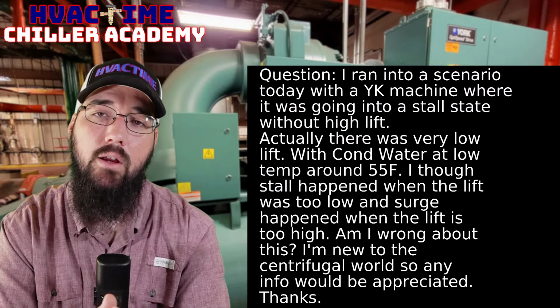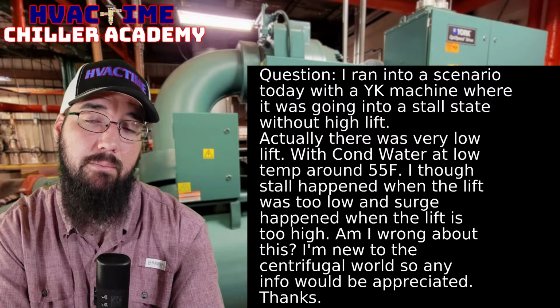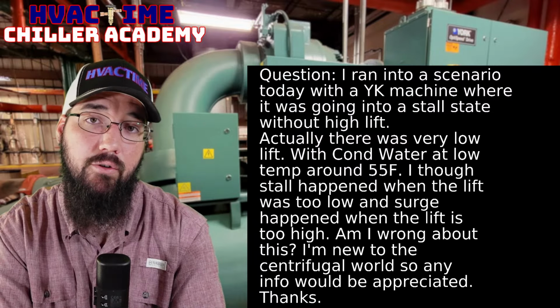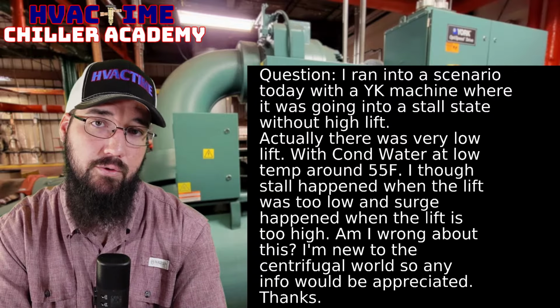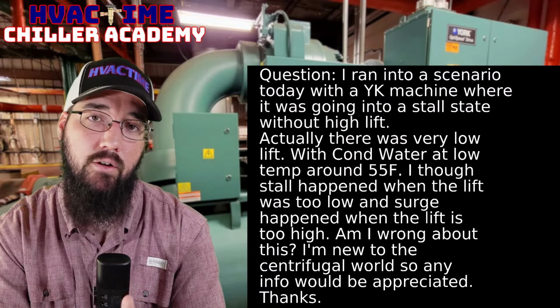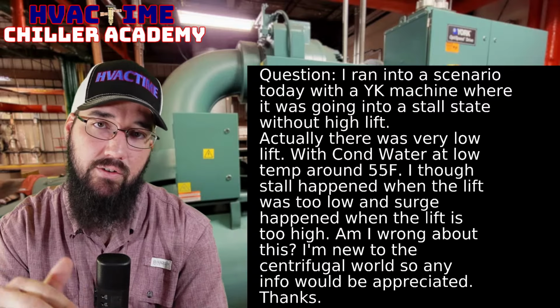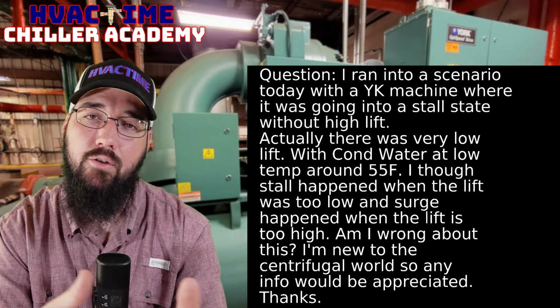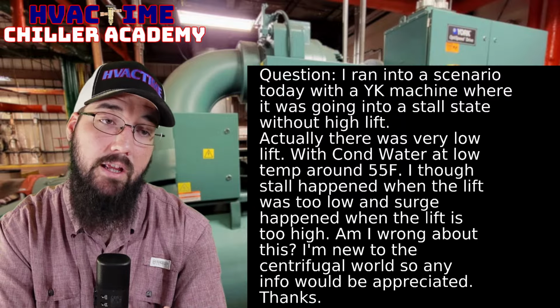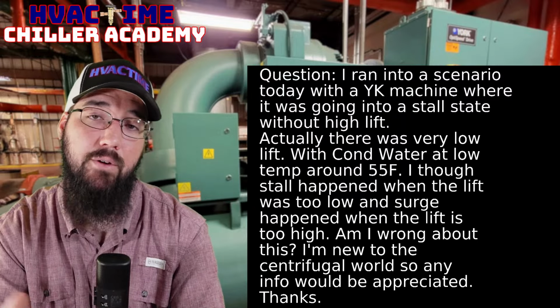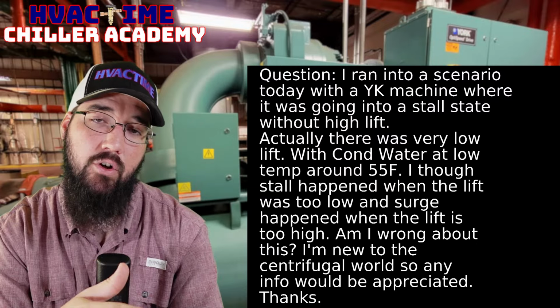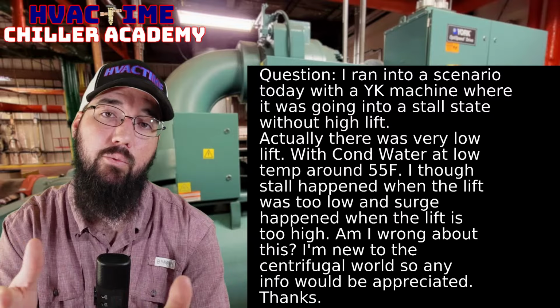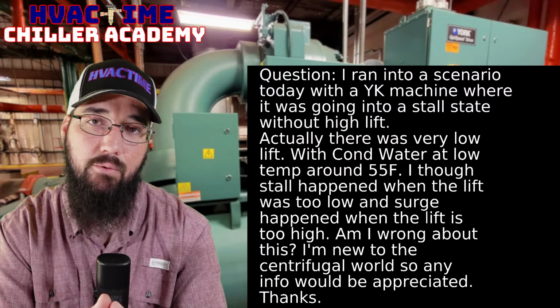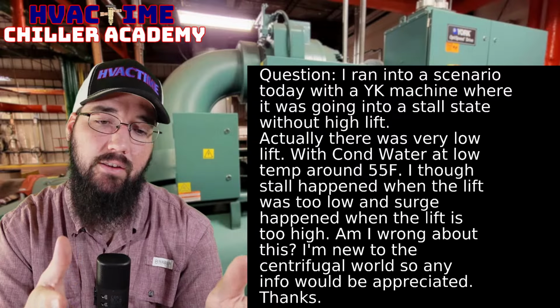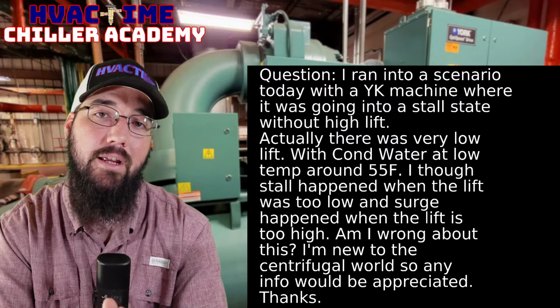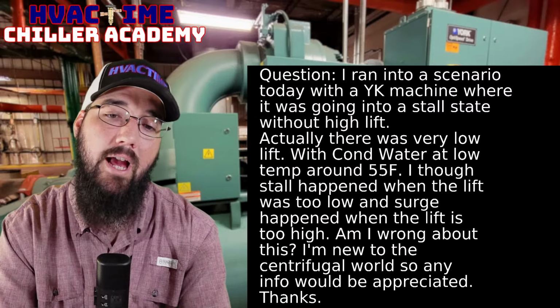Now keep in mind though, your approach may have originally been half a degree, 1 degree, and it may not be excessive approach, right? So in this scenario, when we start having that oil interfering with us, as we start seeing it stack in the evaporator, it may not mean you're running 4 or 5 degrees plus approach. It may mean you went from 1 degree to 2.5, but nothing else changed. You just saw that approach value slowly increase with runtime, even though the load and everything else stayed relatively the same.